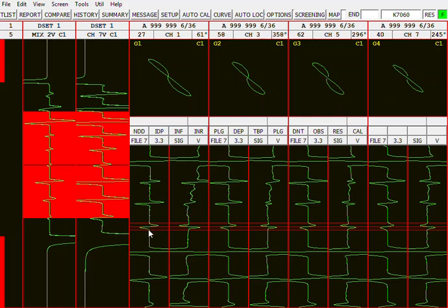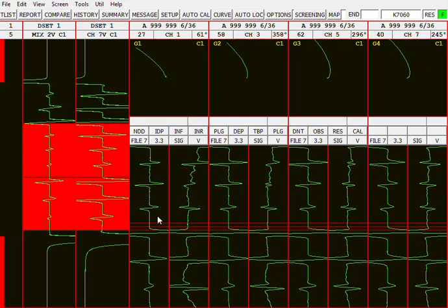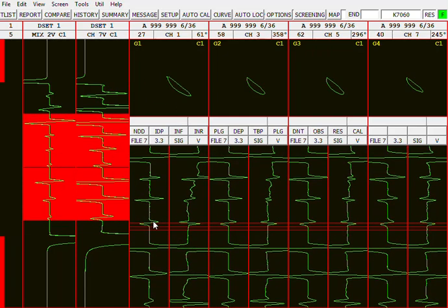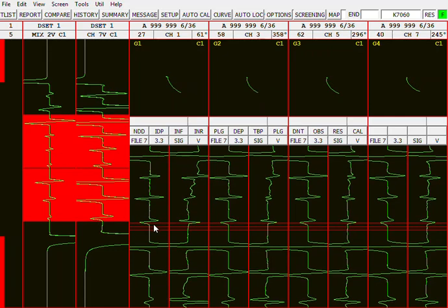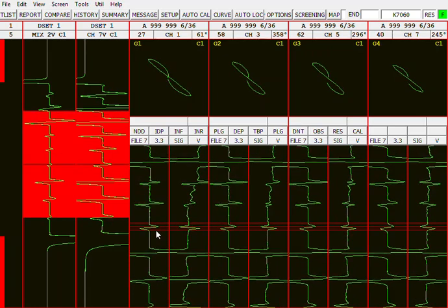So notice how, if you look on the vertical, negative is down, positive is right. And on the horizontal strip chart, left is over here and right is over here. So looking at the signatures in the expanded strip chart, they go down and to the right. So you can kind of tell what the signal is going to look like just by looking here. But just to confirm that, while I scroll into the window, watch the Lissajous down and to the right. And then the back half of the signal is going to go positive here and to the left. So watch when I scroll that down. That's when your second differential coil sees it. So these are all calibrated down to the right, down to the right, down to the right.